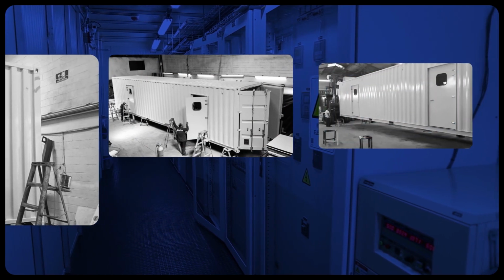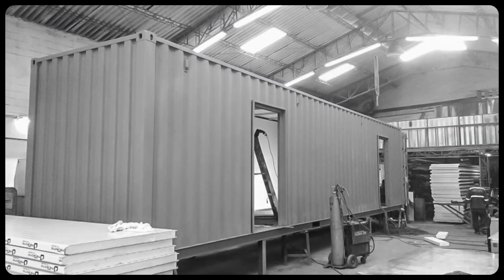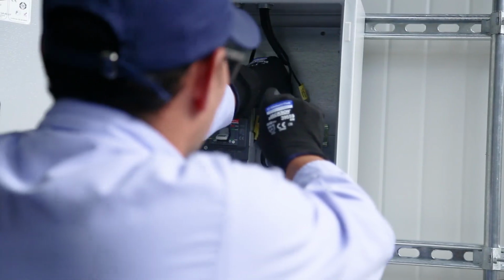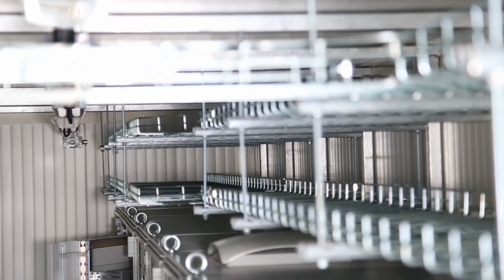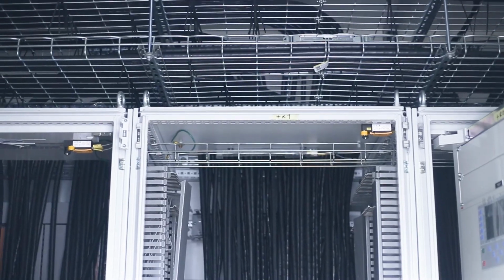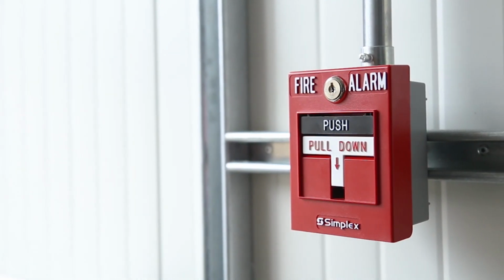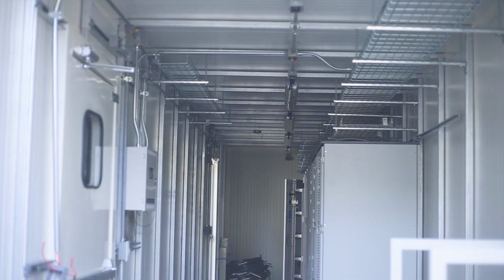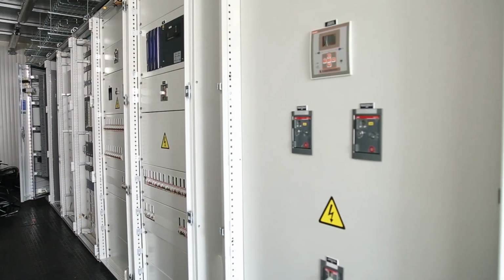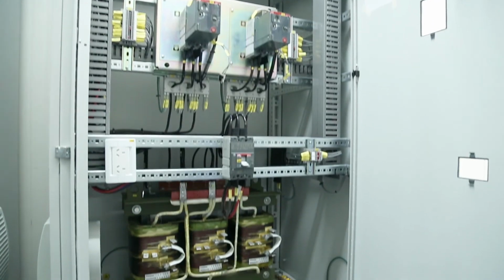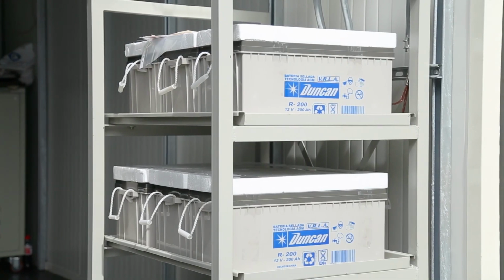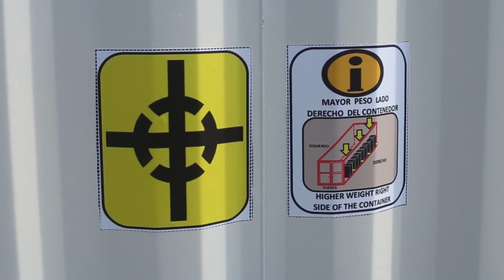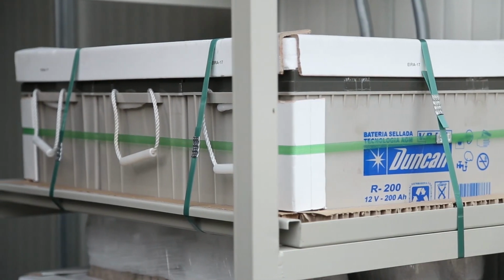In addition to the board assembly process, the manufacture of a prefabricated control building comprises adequacy of the enclosures, installation of complementary systems such as lighting, power supply, air conditioners, cable trays, and detection or fire extinguishing system, installation of control, protection, and auxiliary services cubicle inside the container, including auxiliary services transformer and battery bank, equipment energization and execution of tests, after which proceed with the packing, assurance of internal equipment for transportation, and dispatch of the prefabricated building to site.